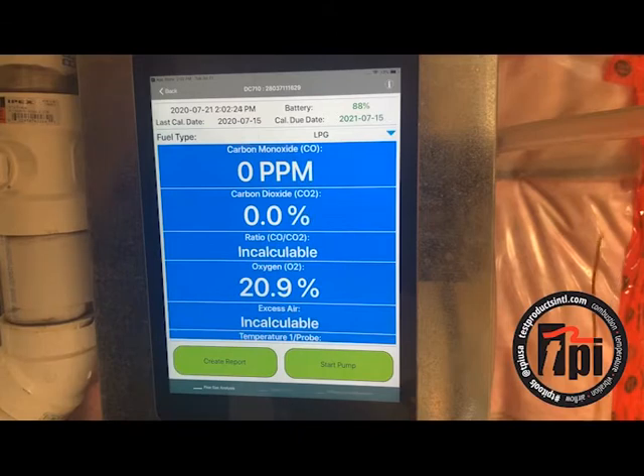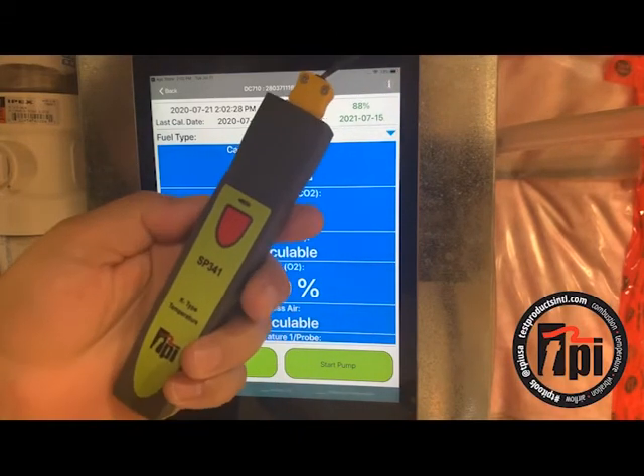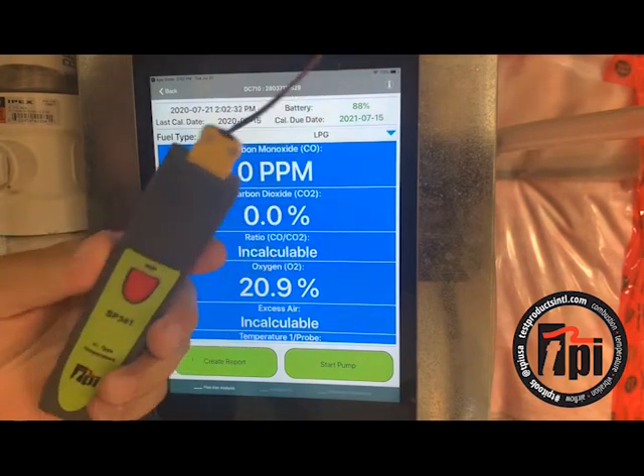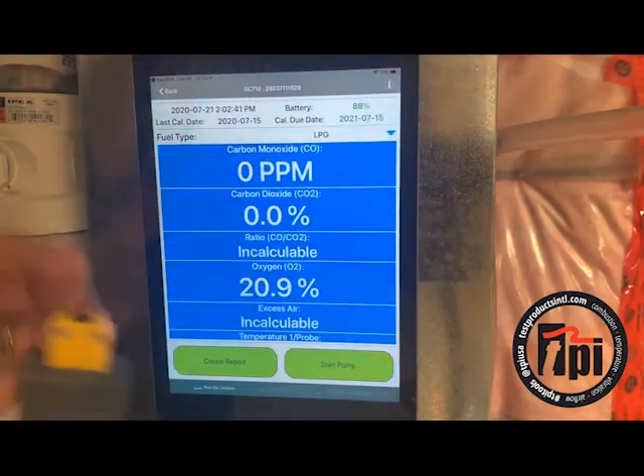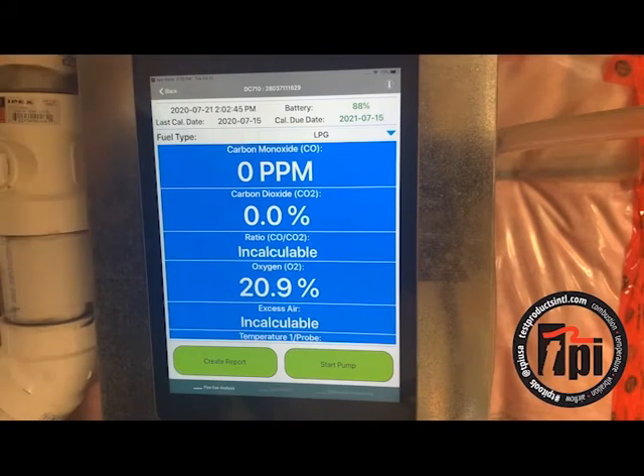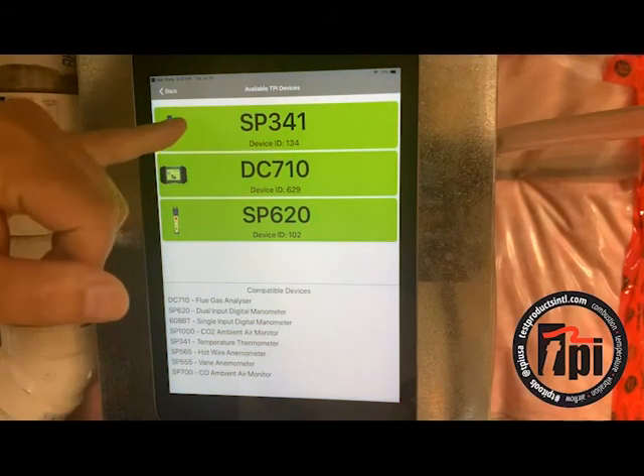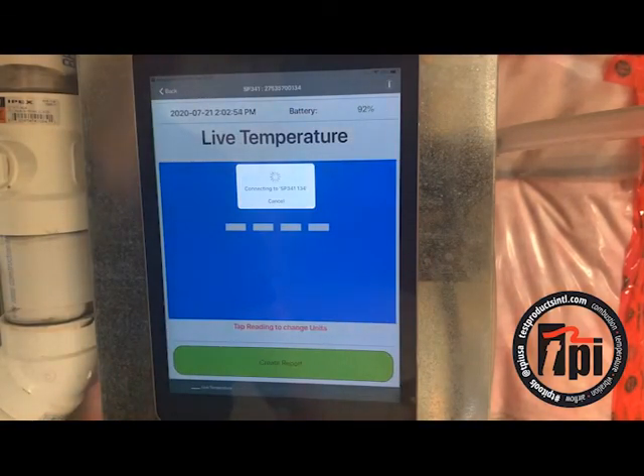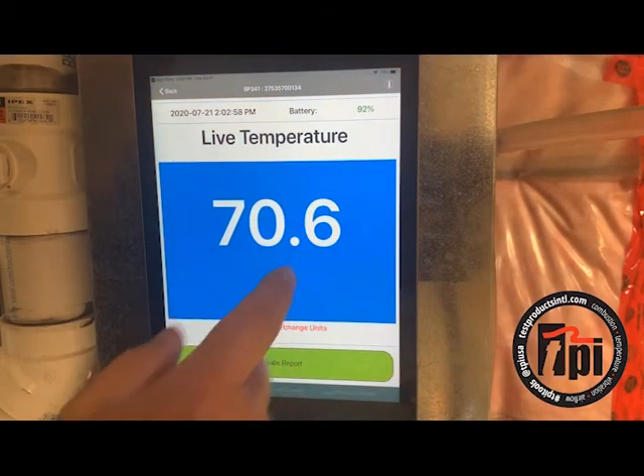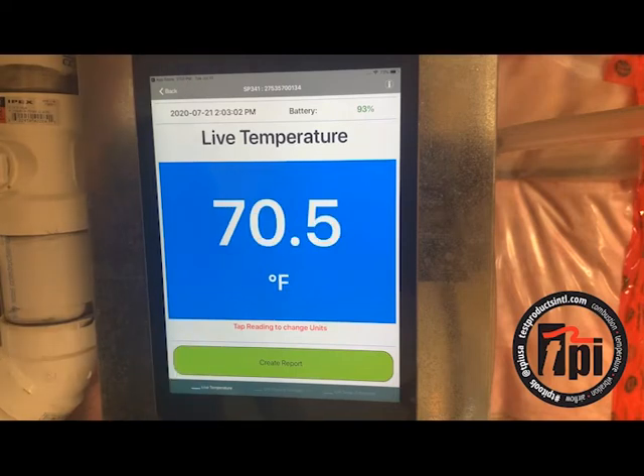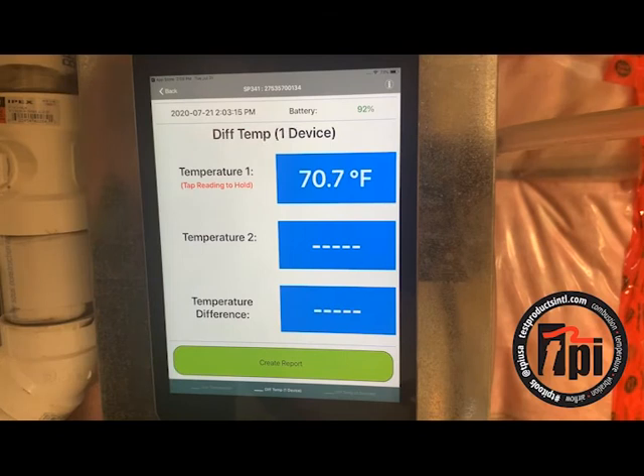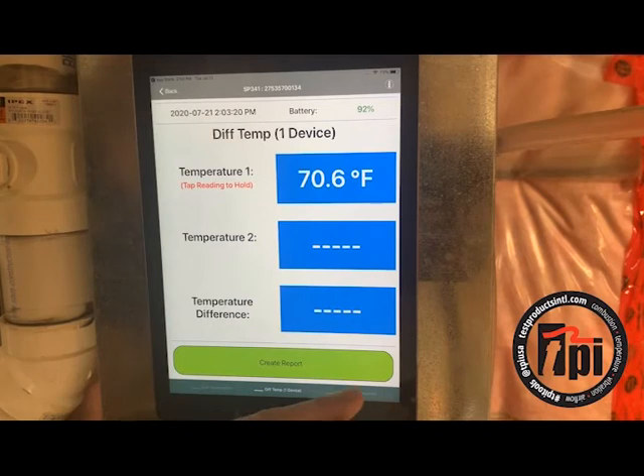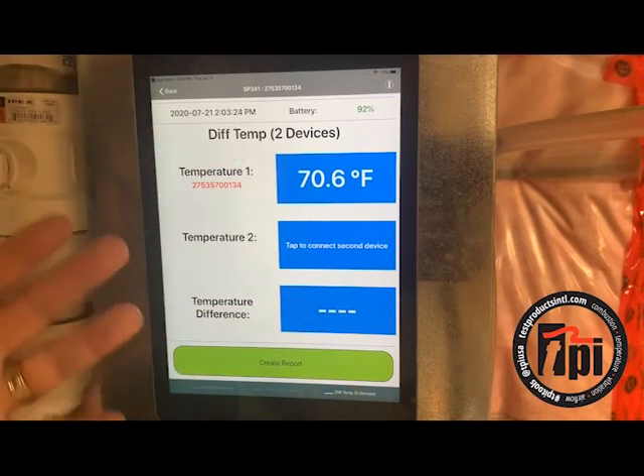One of the other tests I might want to do is temperature heat rise. Here is the SP341 — this is a type K thermocouple. You can plug in any type K thermocouple; these are the ones that come with it, including magnetic ones so you can just stick these in the ductwork. As soon as I turn it on, it is now visible: SP341, measuring temperature right now at 70.6 degrees. Just tap on the screen and it converts to Celsius, or back to Fahrenheit. I can do a single input measurement or go down here and do differential temperature — measuring the temperature, recording it, then moving the thermometer to the other side and recording that temperature to get my Delta T, or I can use two separate temperature devices and measure them simultaneously for the same results.